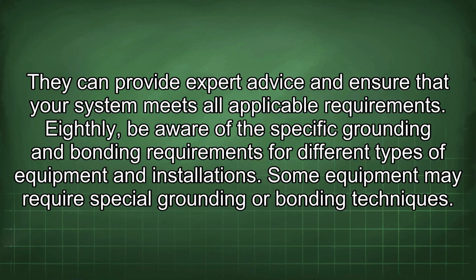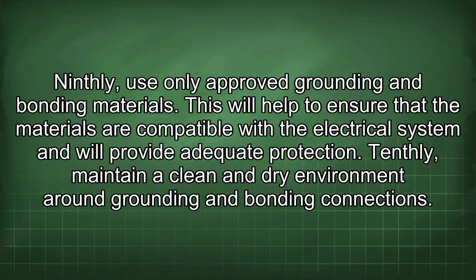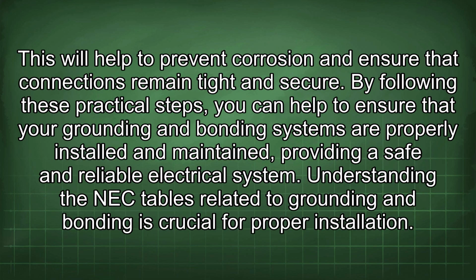Eighthly, be aware of the specific grounding and bonding requirements for different types of equipment and installations. Some equipment may require special grounding or bonding techniques. Ninthly, use only approved grounding and bonding materials. This will help to ensure that the materials are compatible with the electrical system and will provide adequate protection. Tenthly, maintain a clean and dry environment around grounding and bonding connections. This will help to prevent corrosion and ensure that connections remain tight and secure.